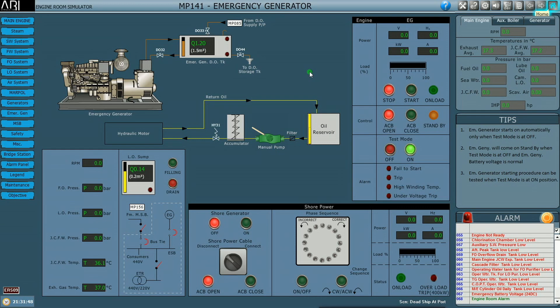Let us see why the emergency generator did not come on load. This is our emergency generator. It will have a minimum of two modes of starting: one with the help of a battery, and the second mode either hydraulic, like what we have in our system. Why this particular generator did not come on load is because it is not on standby.